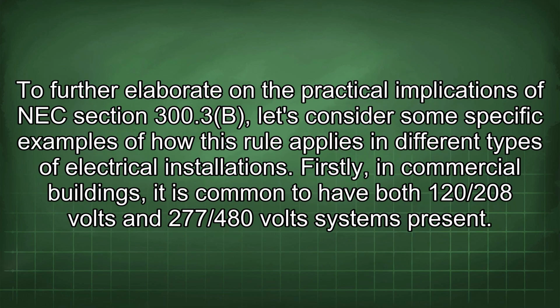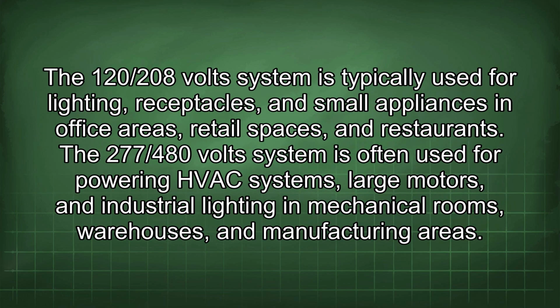To further elaborate on the practical implications of NEC Section 300.3b, let's consider some specific examples of how this rule applies in different types of electrical installations. Firstly, in commercial buildings, it is common to have both 120/208 volt and 277/480 volt systems present. The 120/208 volt system is typically used for lighting, receptacles, and small appliances in office areas, retail spaces, and restaurants.